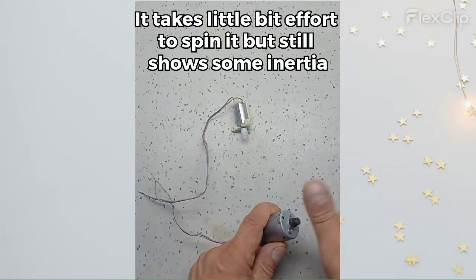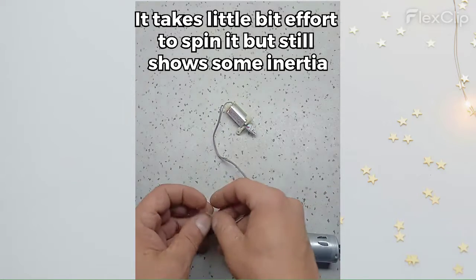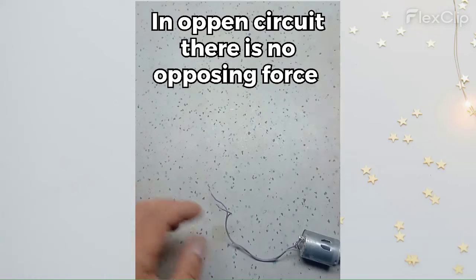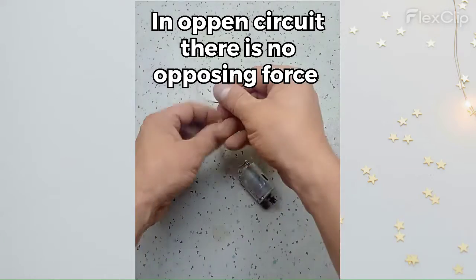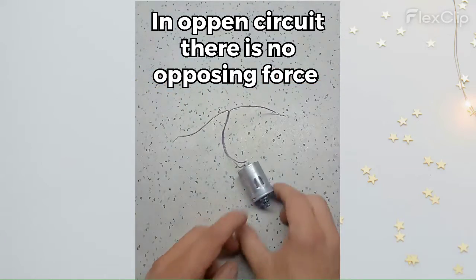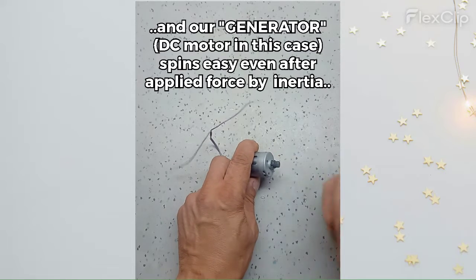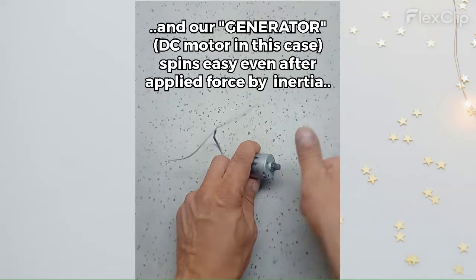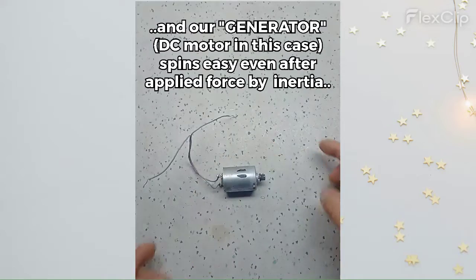Anyone who decides to build a wind or water powered generator must consider that the torque needed to move the turbine blades depends on the output resistance and power consumption of the load. For example, if we mount a wind turbine and leave the output as an open circuit without connecting any appliances or battery charger, it would be easy to move the blades at almost any wind speed. The turbine will rotate regardless of its size and power.